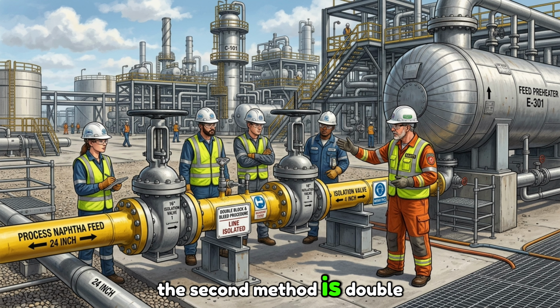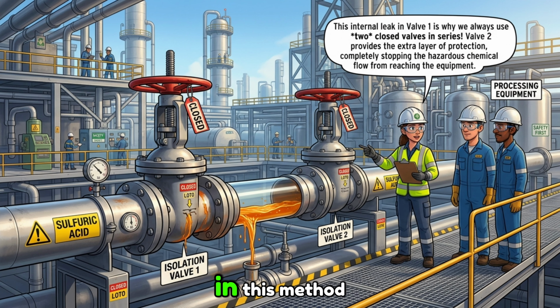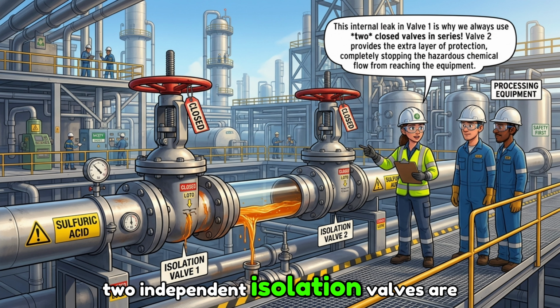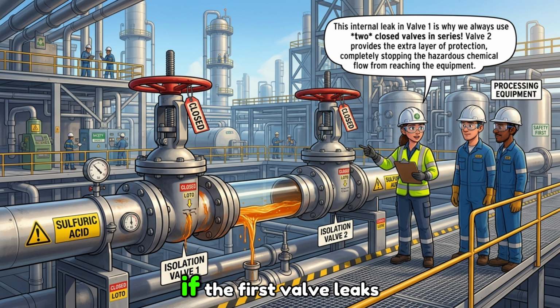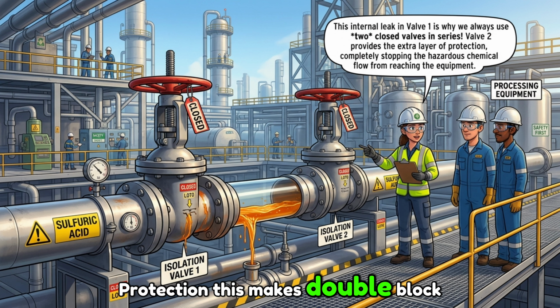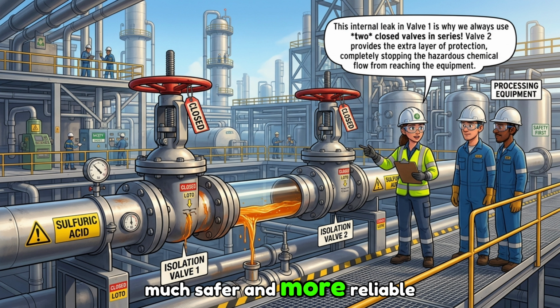The second method is double block isolation. In this method, two independent isolation valves are closed. If the first valve leaks internally, the second valve provides an additional level of protection. This makes double block isolation much safer and more reliable than single block isolation.